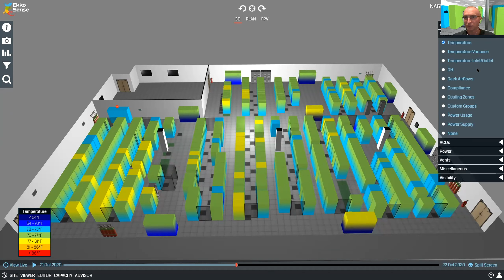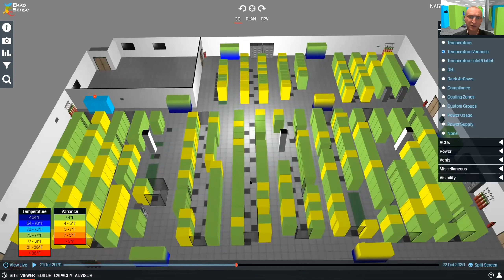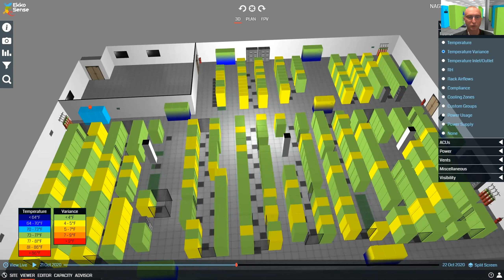If you wanted to see temperature variance, for example, this is a very quick and easy way of seeing the difference across the inlet side of any racks. That's a good way of understanding airflow issues near a rack. As it gets hotter, the variance gets wider, which can indicate airflow issues in particular areas of the room that need investigating.